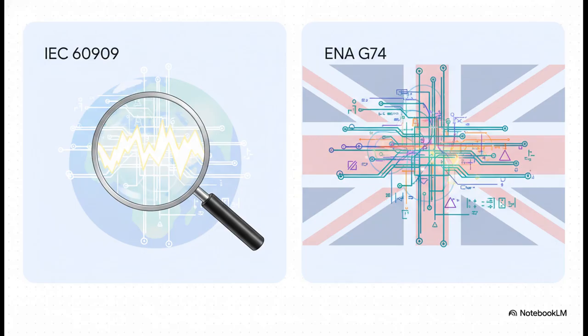Now, the two main standards in play here are the international IEC 60909 and the UK's ENA G74. And the big difference comes down to how they figure out the pre-fault voltage. IEC 60909 uses these simplified, intentionally conservative C factors, basically just a voltage multiplier to be on the safe side. ENA G74, on the other hand, is a bit more sophisticated. It uses a full load flow calculation to get a more accurate pre-fault voltage, which almost always gives you a more realistic and usually lower fault level.